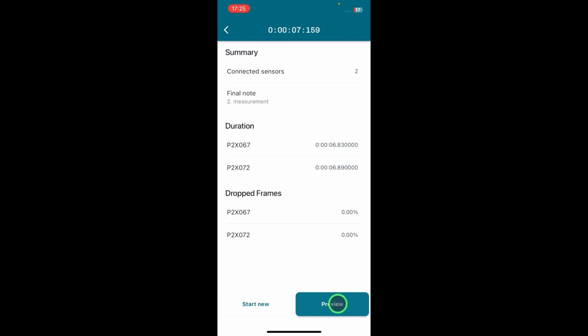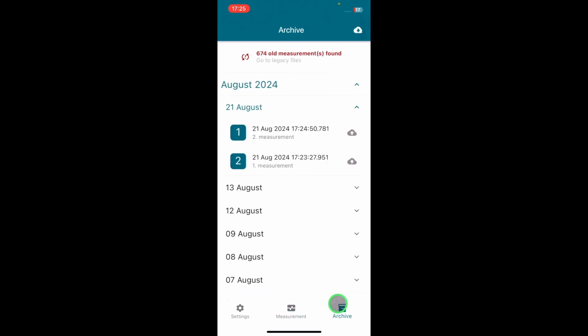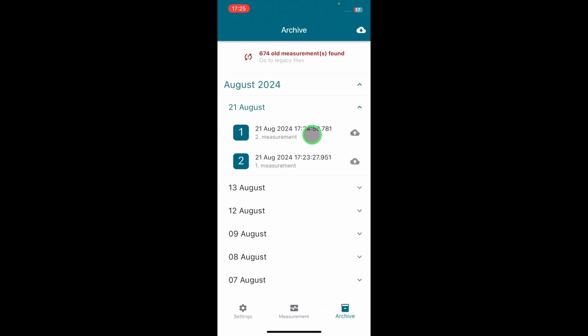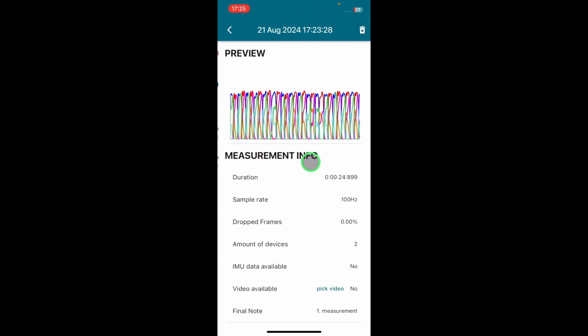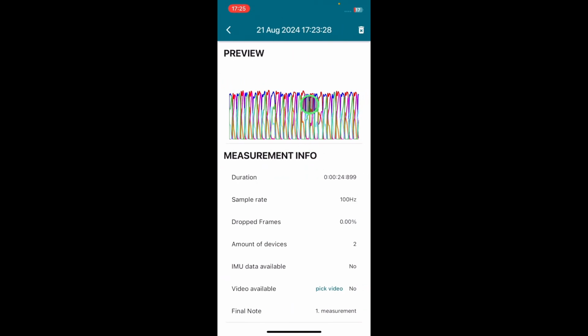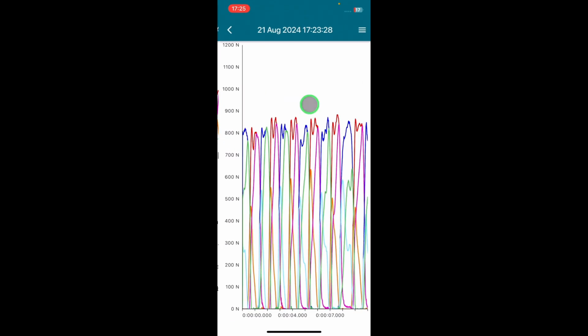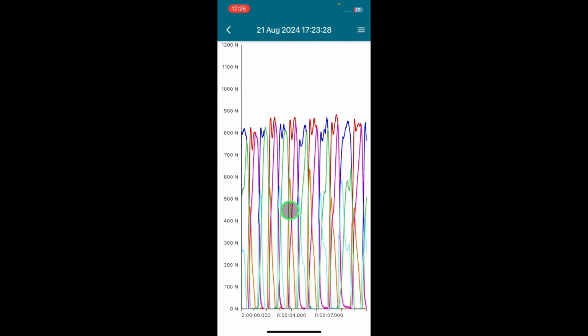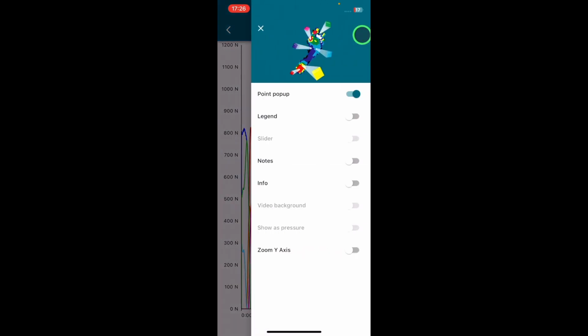If you would like to go to a preview of the previously measured data, you go on preview and one can see here the sequence of measurements done today. Here there is also the starting time of the measurement, and please note that always the latest measurement is on top. So if you want to go here, you just select this one, and now you can look at the individual data by just clicking on that, and here we can see now the total curves and the sub areas. By selecting the menu, you can switch on the legend, which allows you also to switch the individual curves on or off for the display.